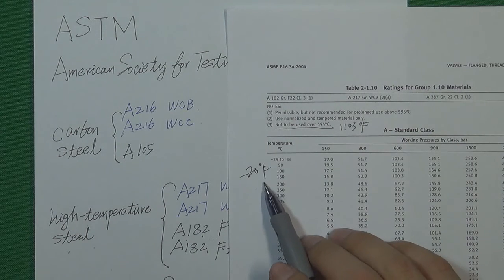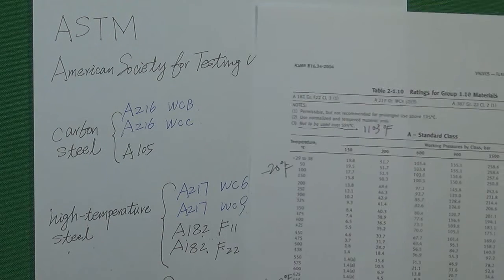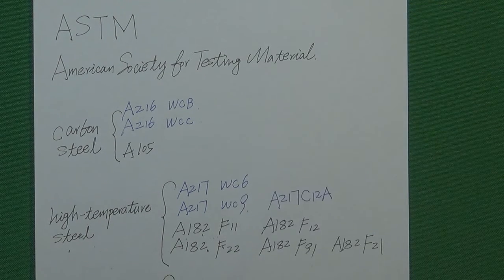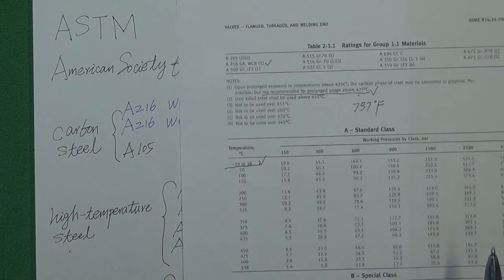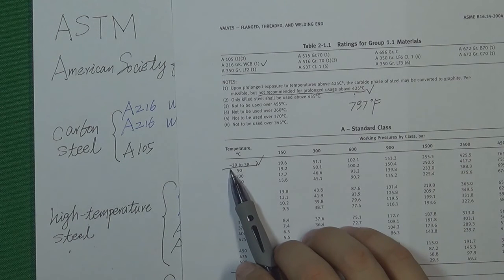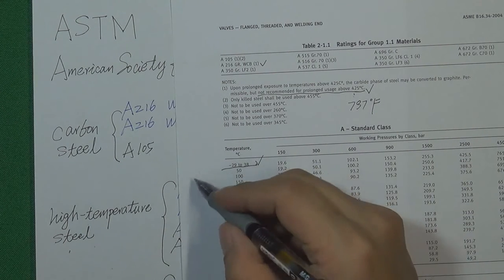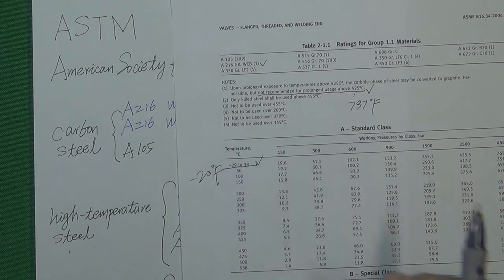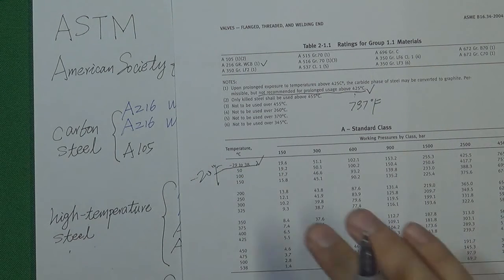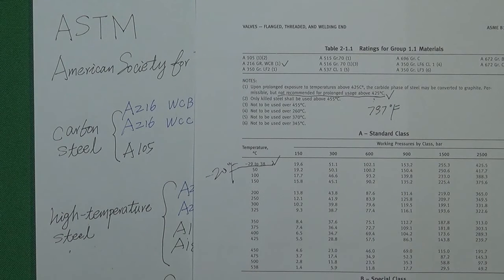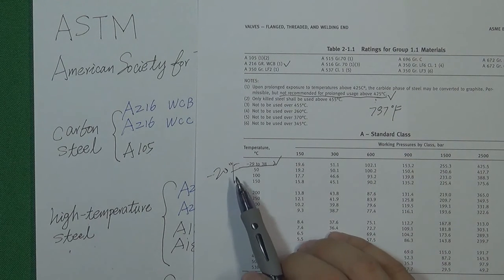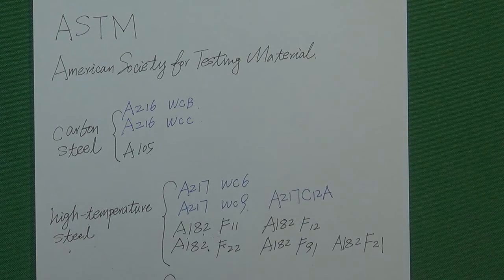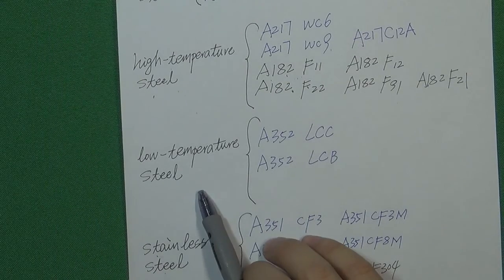That is the minimum temperature for the WC9. And for the carbon steel like the WCB, the minimum temperature is the same — minus 29 Celsius degree, which also equals minus 20 Fahrenheit degrees. So this kind of material cannot work in a low temperature environment below that. So material engineers invented a kind of material called low temperature steel.